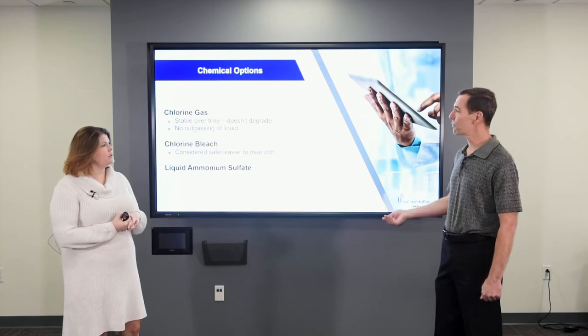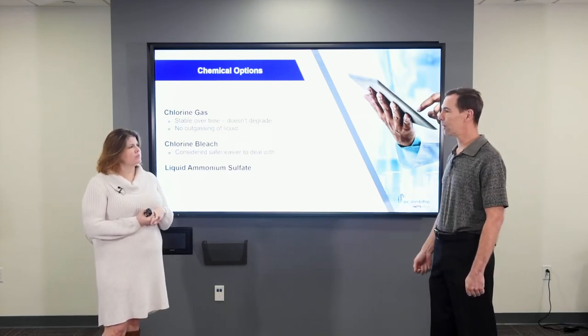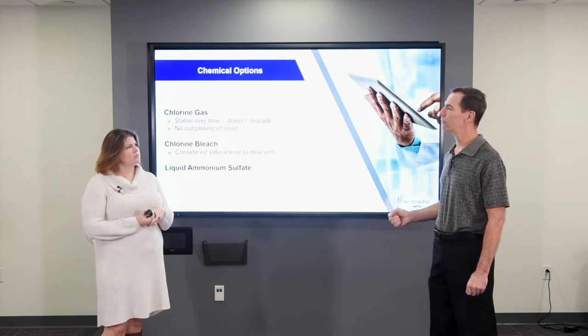One of my customers runs a fairly small plant — about 200,000 gallons per day. During production, their ammonia, their LAS feed, is like 3 milliliters per minute — a trickle. That plant actually shuts down at times and turns back on automatically. Early on, one of the problems I identified was that when the plant was shut down, a little bit of water would creep back into the injection quill and the tubing at the injection point. Even though there was a check valve at the chemical pump itself, there's a little flex in the tubing, maybe a little leak-by. If you have a foot of tubing filled with water and you're only flowing 3 milliliters per minute, it's going to take a while to flush that back out.